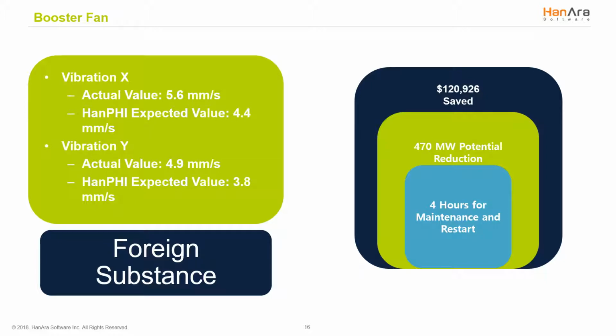The sixth case occurred in May 2016 when HanPHI helped an 870 megawatt thermal power plant save approximately $121,000 in maintenance and operation costs by preventing a booster fan failure. On May 26, HanPHI identified irregular increases in the booster fan vibrations. Within 4 hours, a booster fan vibration X increased to 5.6 millimeters per second, when HanPHI expected the vibration to be at 4.4 in the plant's current condition. A vibration Y also increased to 4.9 when HanPHI expected 3.8 millimeters per second.